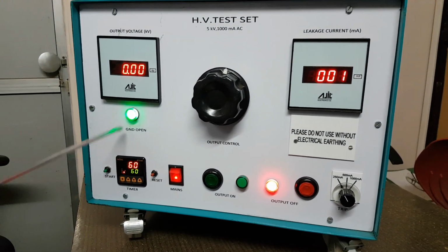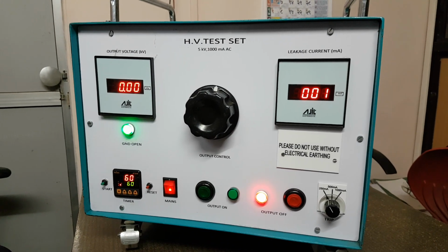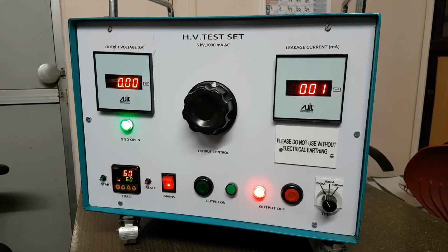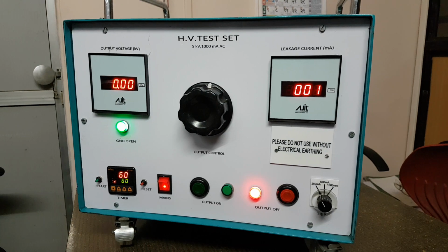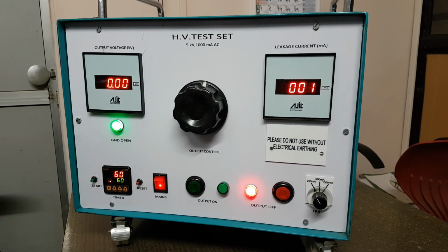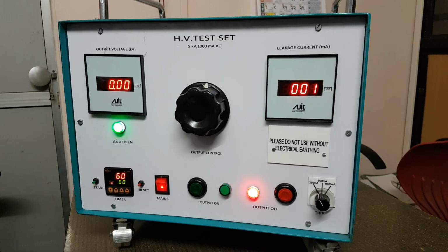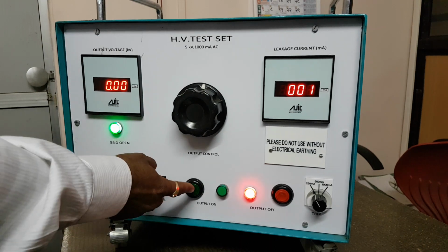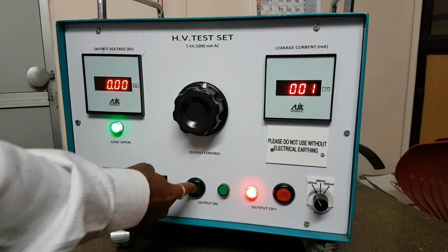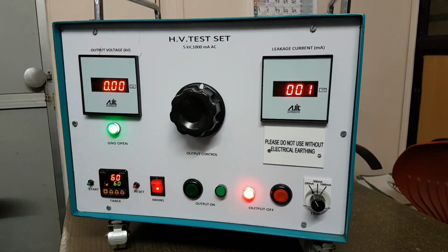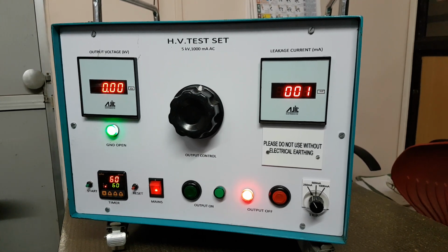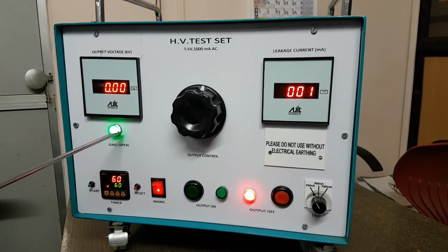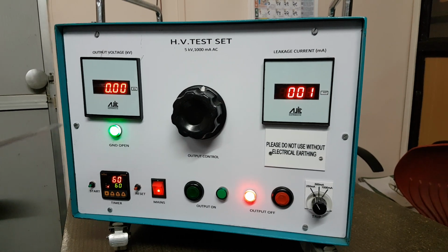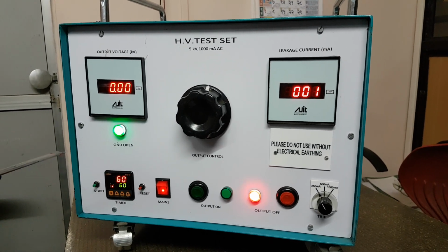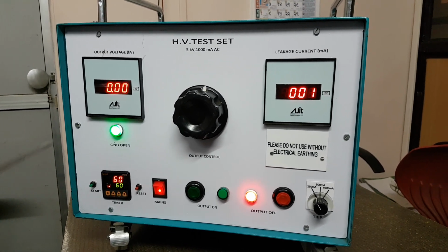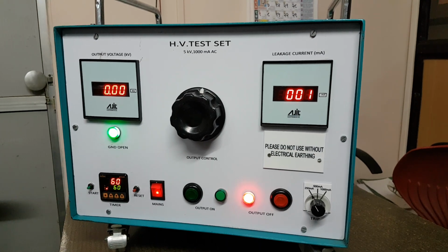But this indication shows that the instrument is not connected to earth properly or the ground properly. That is the reason this lamp is coming up and the high voltage cannot be initiated. It is not getting started. So we have to first check this interlock. We have to connect earthing properly to the instrument, and then again we have to put on the instrument and check.